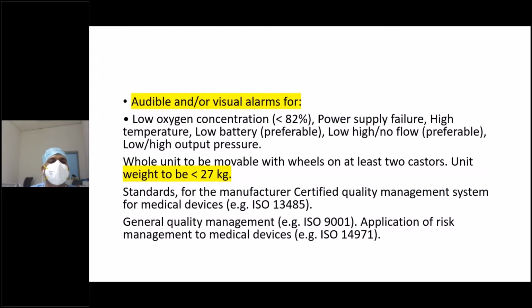And it should have an audio and visual alarm for low oxygen concentration. If concentration goes below 80%, there should be an alarm. It should also have alarms for power supply failure, increased temperature, low battery if it has an inbuilt battery backup, and low, high or no flow pressures. And the weight of the machine should not be more than 27 kg.